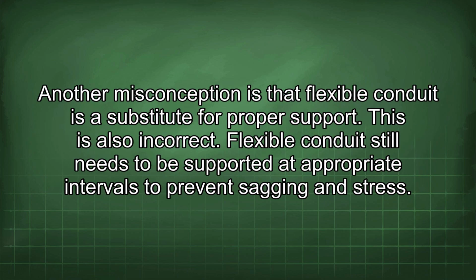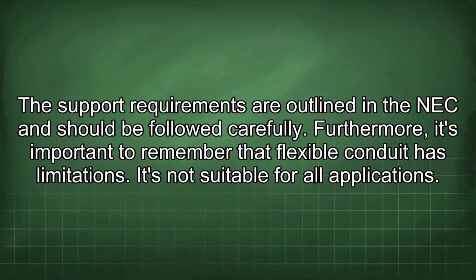Another misconception is that flexible conduit is a substitute for proper support. This is also incorrect. Flexible conduit still needs to be supported at appropriate intervals to prevent sagging and stress. The support requirements are outlined in the NEC and should be followed carefully.